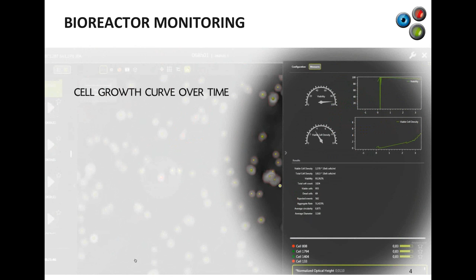This measurement is based on the lens behavior of a cell. To simplify things, a healthy, live cell will create a light cone, so it will concentrate the light in an out of focus point, and a dead cell with a porous membrane will diffuse light. We combine that with the dry mass measurement of the cell and the average size, etc. We also have software with similar functionality to a flow cytometer. The green dots represent the living cells. The red dots represent the dead cells, and you will also see yellow dots, which are cell aggregates. So we also measure the number of cells that are aggregated.